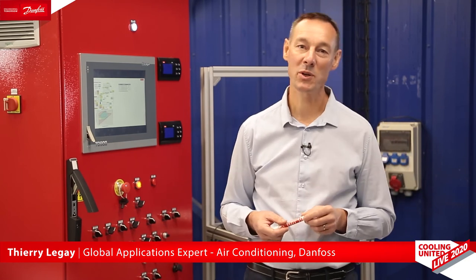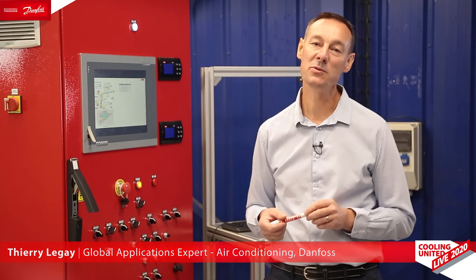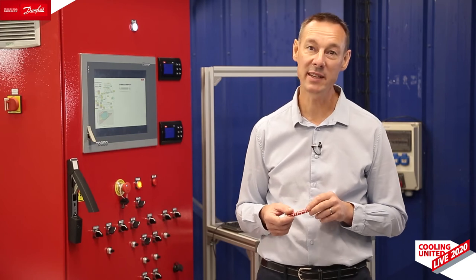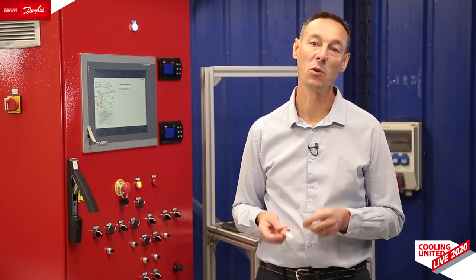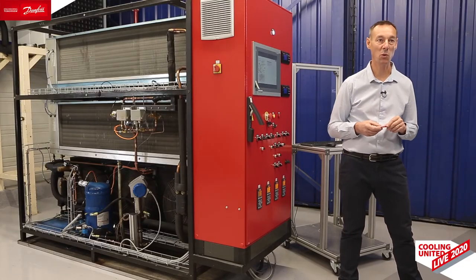Thank you, Arne. Hello, my name is Thierry Legay. I'm a compressor and application expert in Danfoss Cooling. In order to facilitate your design job, Danfoss has developed libraries that facilitate integration of variable speed compressors in your unit. Those libraries cover the most important functions to protect the compressor, like envelope control, oil return control, or discharge temperature control. Let us take the example of envelope control.